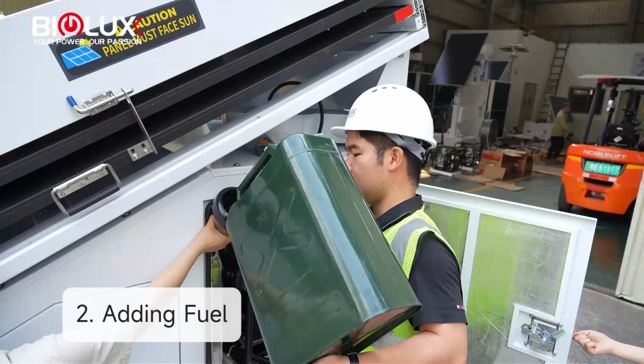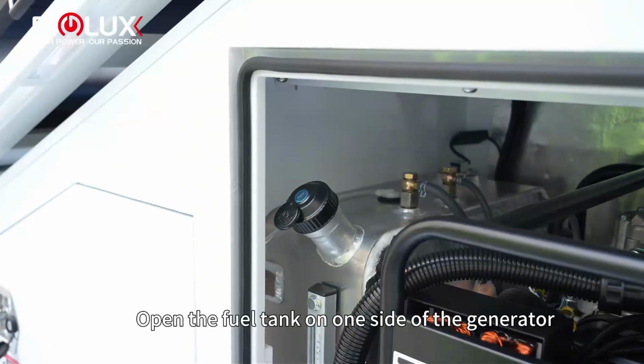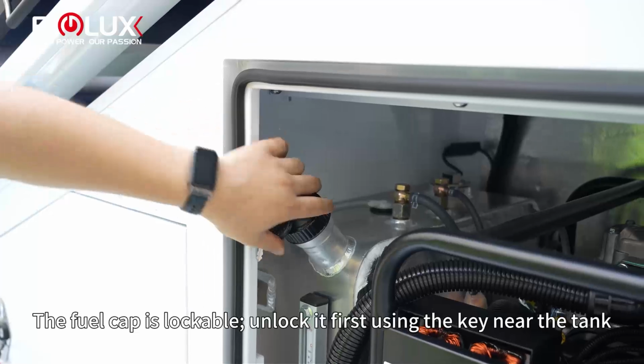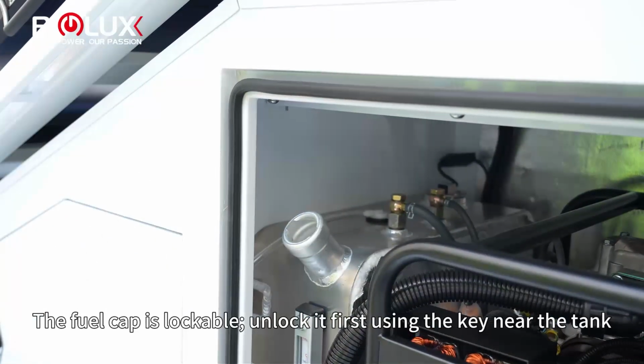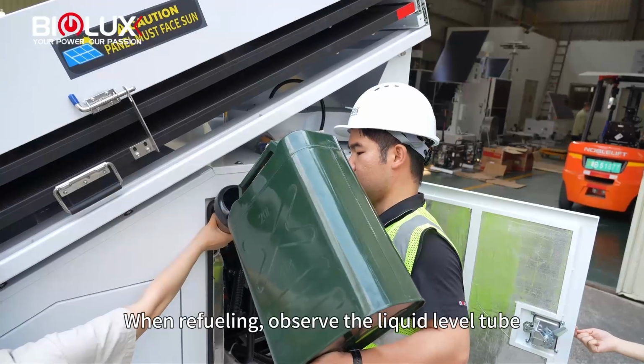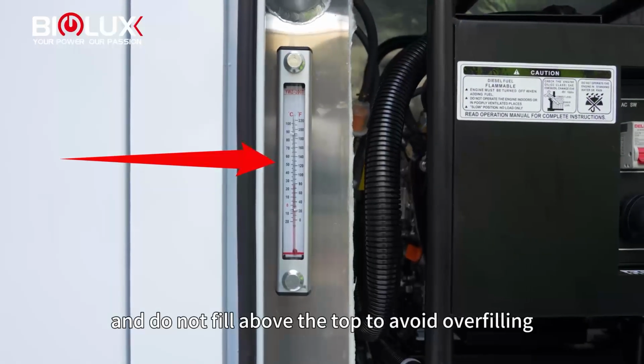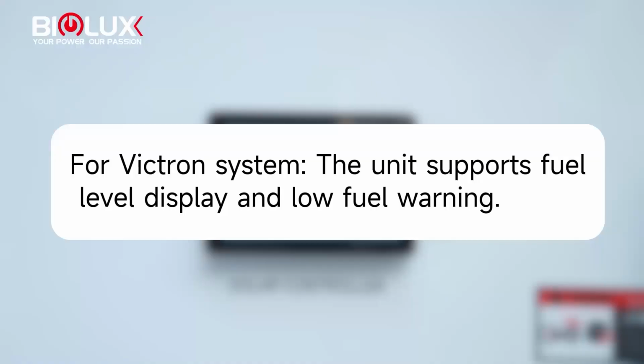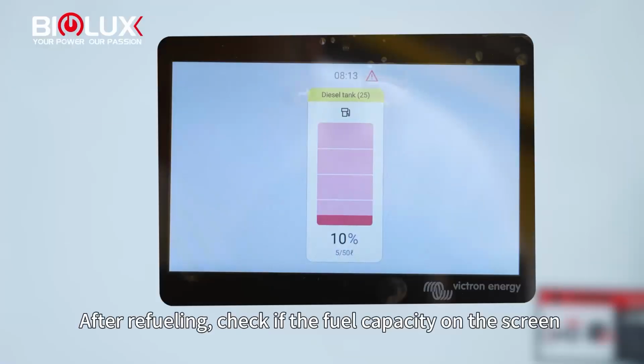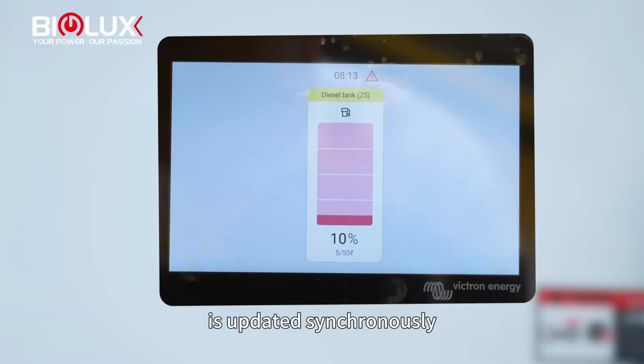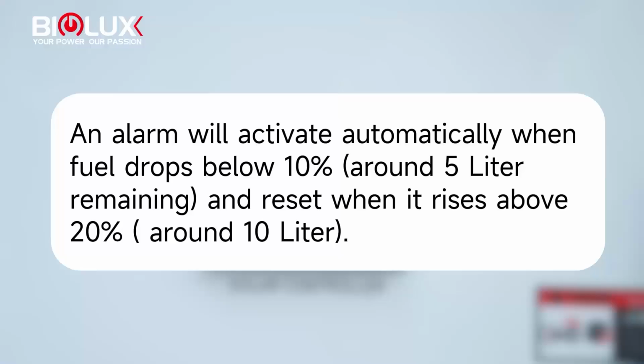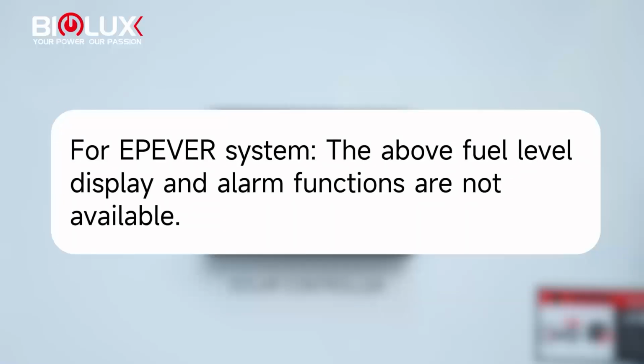2. Adding fuel. Open the fuel tank on one side of the generator. The fuel cap is lockable. Unlock it first using the key near the tank. When refueling, observe the liquid level tube, and do not fill above the top to avoid overfilling. For Victron system, the unit supports fuel level display and low fuel warning. After refueling, check if the fuel capacity on the screen is updated synchronously. An alarm will activate automatically when fuel drops below 10%, around 5 liter remaining, and reset when it rises above 20%, around 10 liter. For an EPEVER system, the above fuel level display and alarm functions are not available.